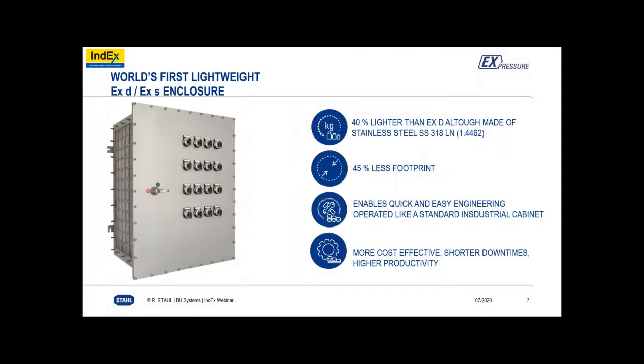Do you want to tell us about the technology and the advantages? What are the main advantages, would you say, of the R.Stahl ExPressure? Through the mesh and through the much lower overpressure in the enclosure, one of the advantages is that you need a significantly lower wall thickness. We're talking here about from 2 millimeters. And this opens the possibility that the enclosure can be much lighter than a conventional EXD enclosure.